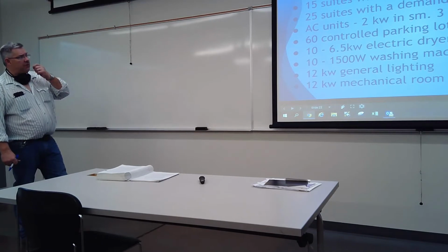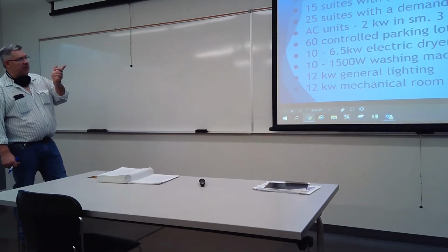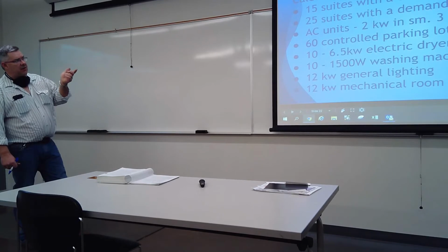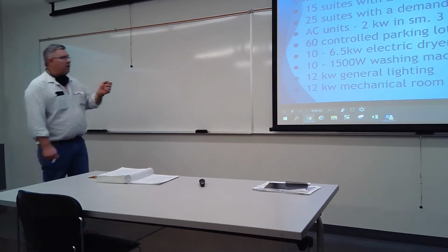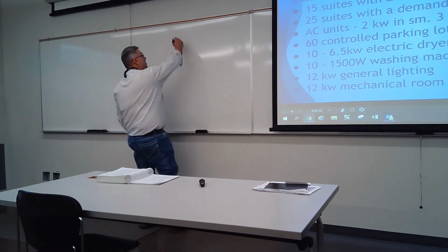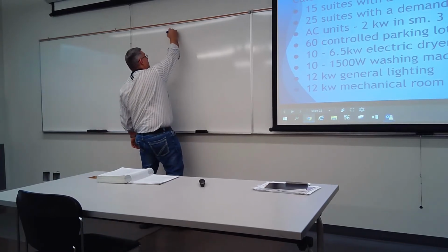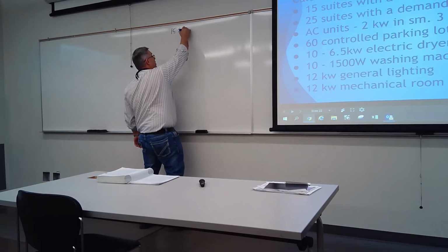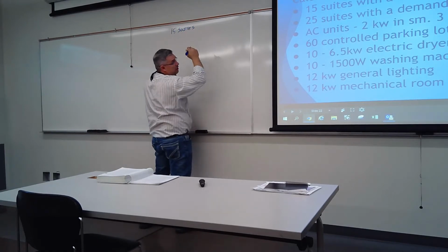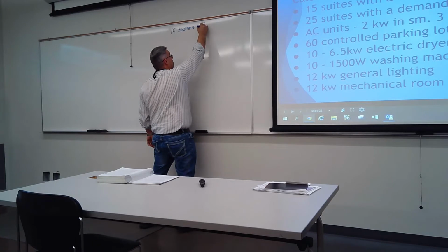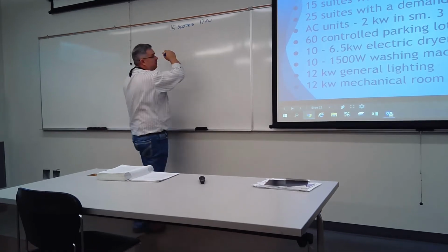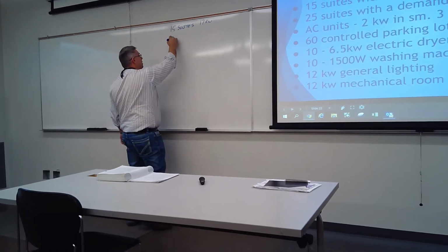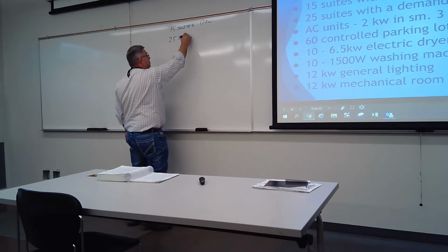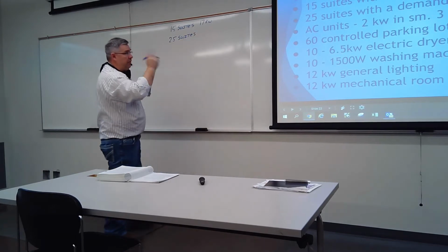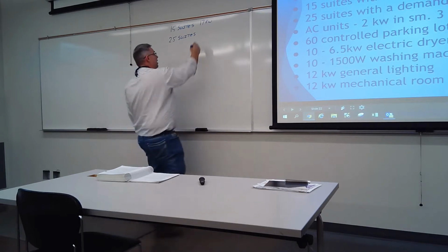So we got 15 suites with a demand of 20 kilowatts. In those suites is a 3 kilowatt air conditioning unit. So we actually have 15 suites with a demand of 17 kilowatts. And we have 25 suites that have a demand of 16 minus 2, which is 14 kilowatts.